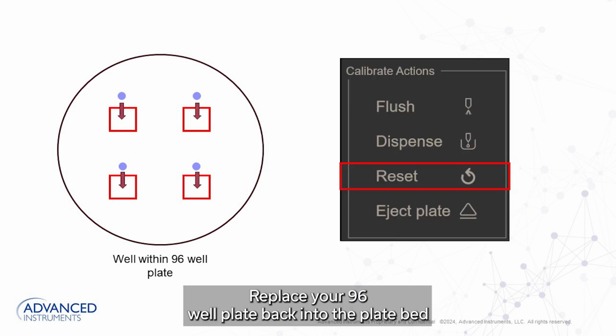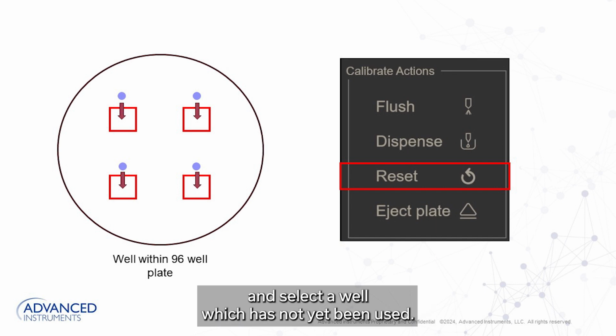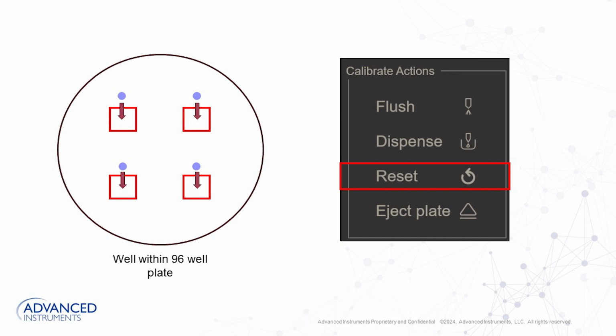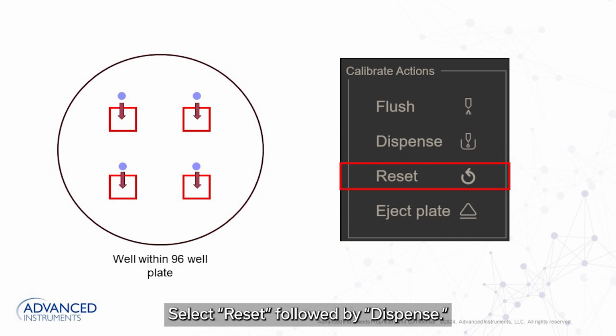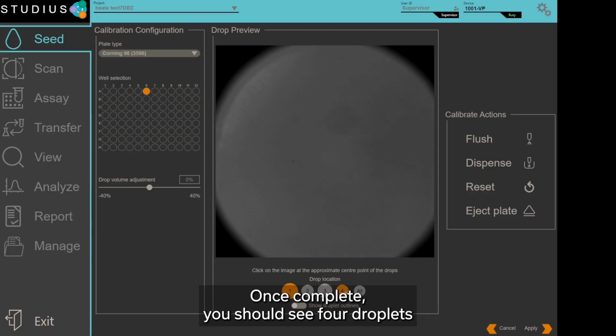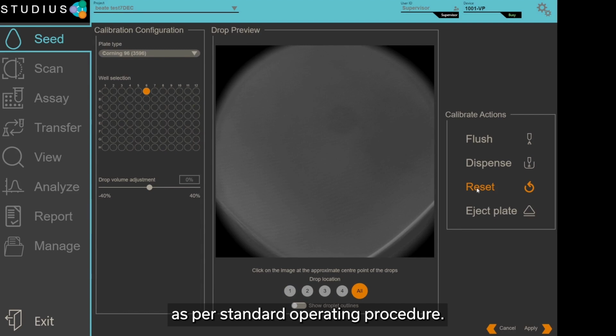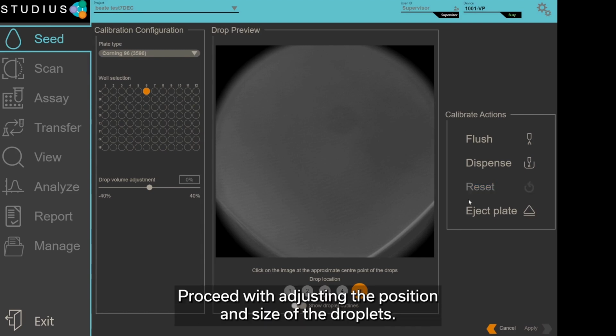Replace your 96 well plate back into the plate bed and select a well which has not yet been used. Select Reset followed by Dispense. Once complete, you should see 4 droplets as per standard operating procedure. Proceed with adjusting the position and size of the droplets.